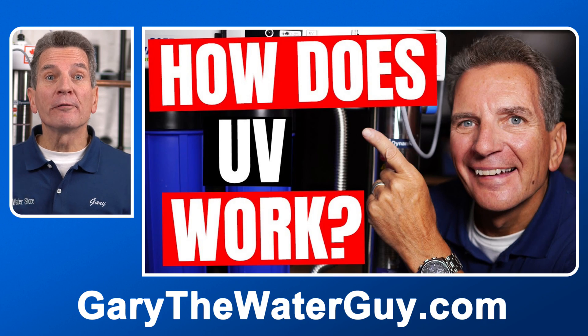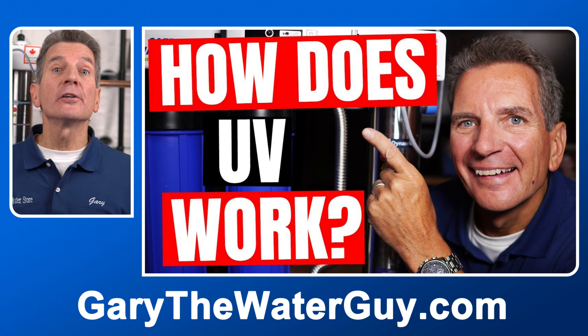Before we go any further, if you're not 100% sure how these ultraviolet disinfection systems work, I definitely encourage you to check out my video — I'll put a link in the description down below. There are some pre-treatment requirements to make sure your water is compatible with the ultraviolet disinfection system, especially for well water. Your water has to have a hardness of 7 or less, 0.3 parts per million of iron or less, and if you have manganese, it has to be 0.05 parts per million. If you have any of those in your well water, you have to deal with that first.